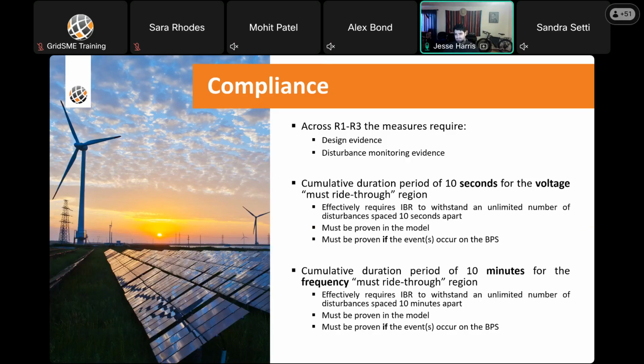For voltage, you have a cumulative duration period of 10 seconds for the voltage ride-through region. So effectively what this is saying is that IBRs are required to withstand an unlimited number of disturbances that are spaced 10 seconds apart, must be proven in the model, must be proven if these events occur on the BPS. Same deal with frequency, except instead of 10 seconds, it's 10 minutes. So it effectively requires an IBR to withstand an unlimited number of disturbances spaced 10 minutes apart.